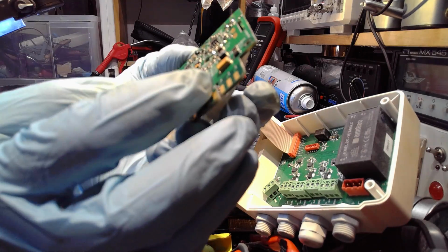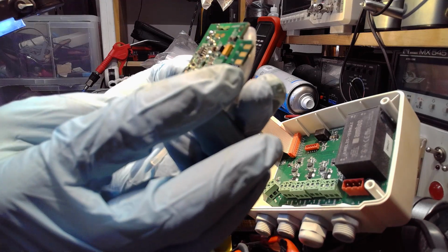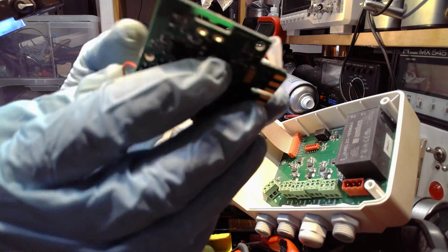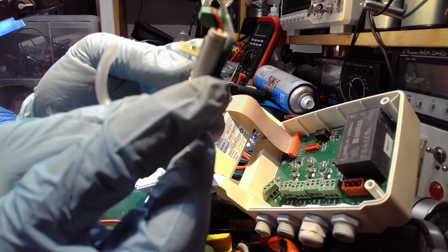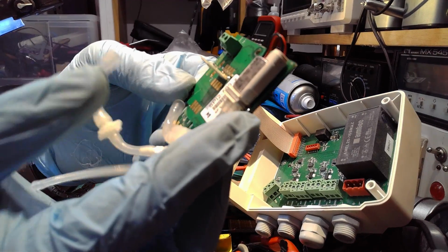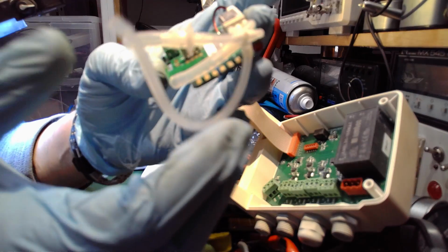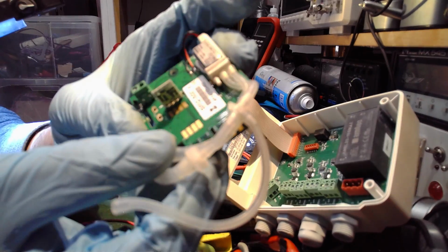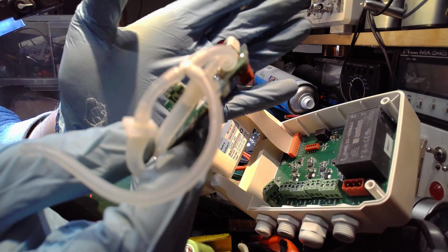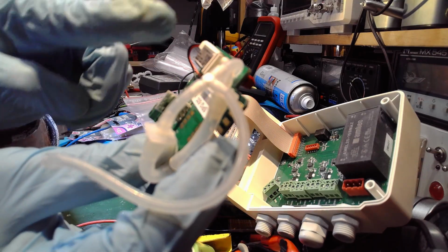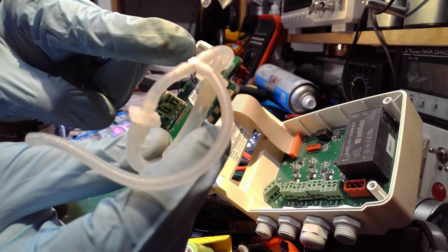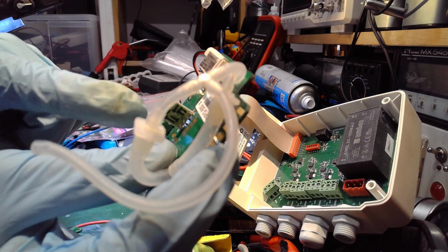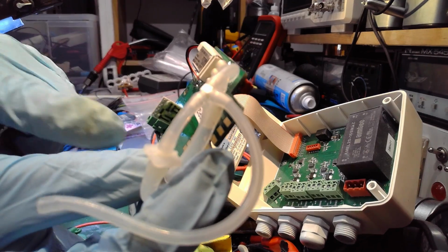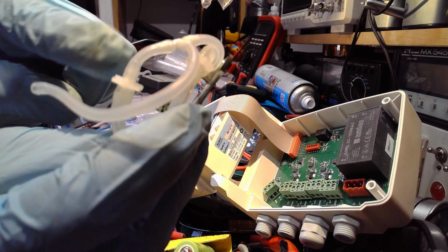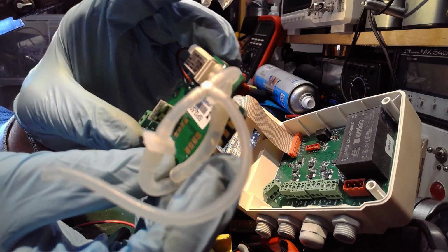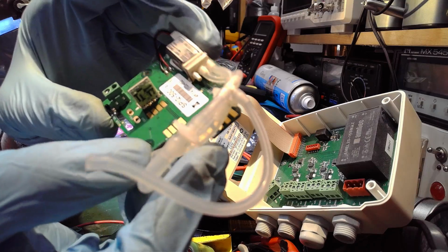You can find here many EEPROM and processor chips to manage the signal. And the particularity of this kind of device is it's able to make its own zero, to calibrate itself, because if you have a drift of the signal, you will have an automatic calibration, and because this valve makes the vacuum between the communication between the HP at entry and the BP at output of this little sensor, it makes this zero automatically to prevent any drift of the signal.